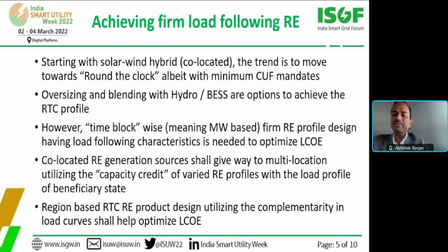Now, time-block-wise, meaning megawatt based, because you need some firmness in terms of megawatt for grid deviation and grid discipline. A firm RE profile needs to have load following characteristics, and that will help in optimizing the levelized cost of energy. Co-located RE generation sources shall give way to multi-location and capacity credit. Some studies were done last year, where the capacity credit of wind resources in Tamil Nadu vis-a-vis Gujarat was studied with the load profile of Delhi. It was found that the capacity credit of Tamil Nadu based wind is more, 60% plus, with the load profile of Delhi.